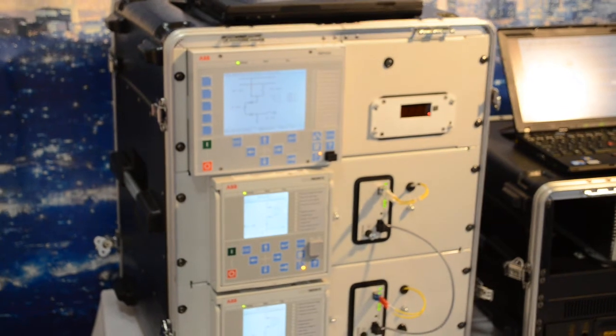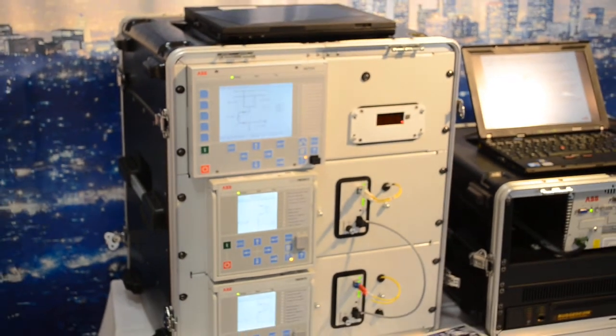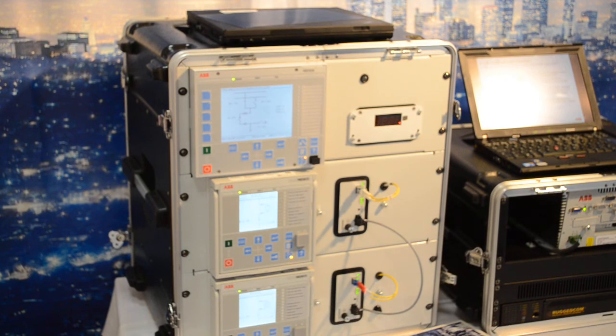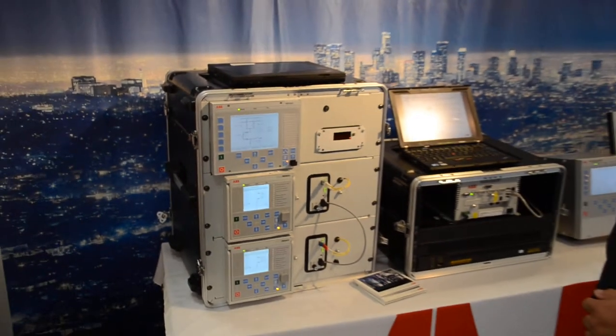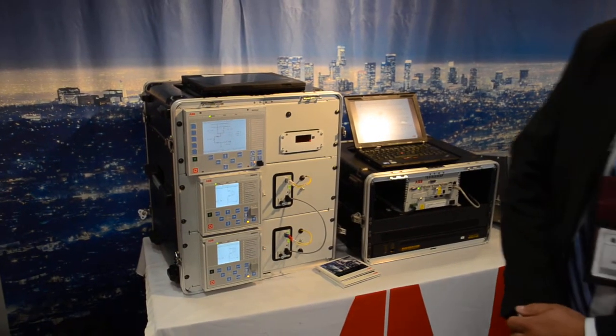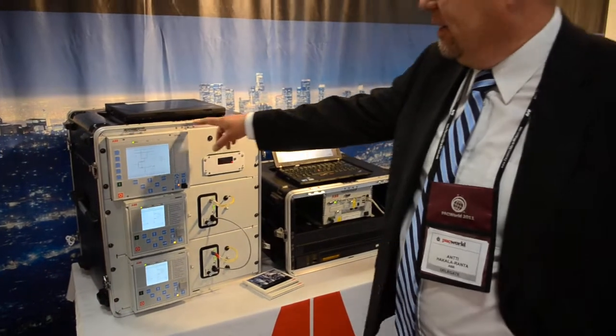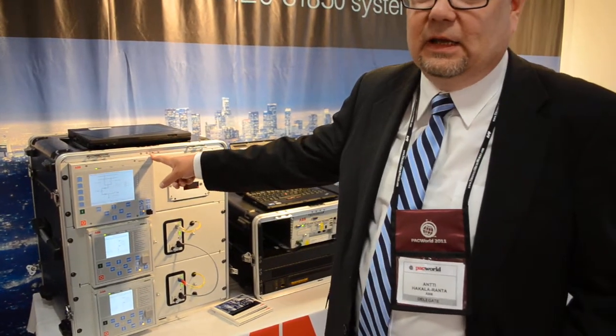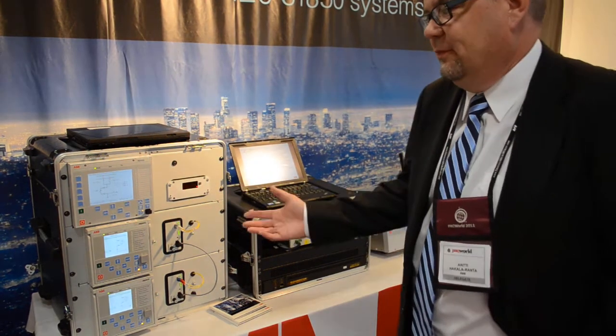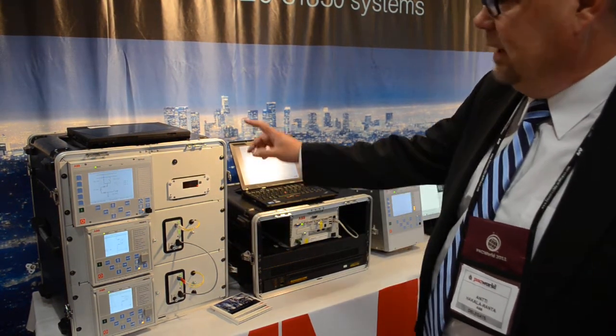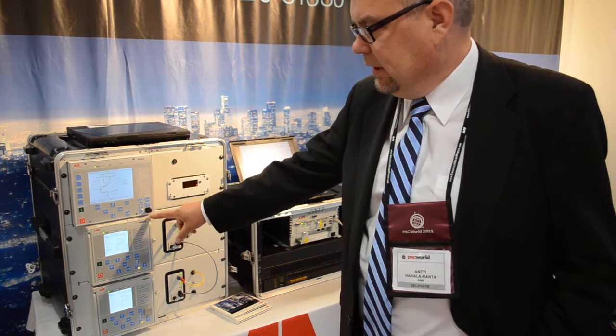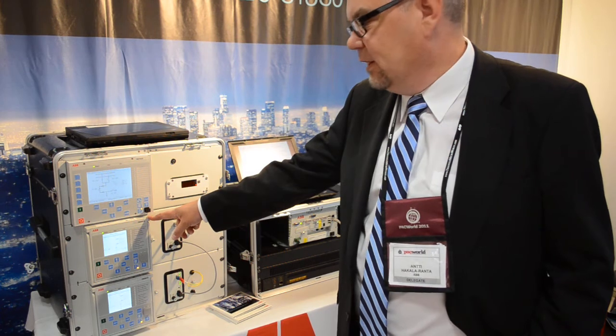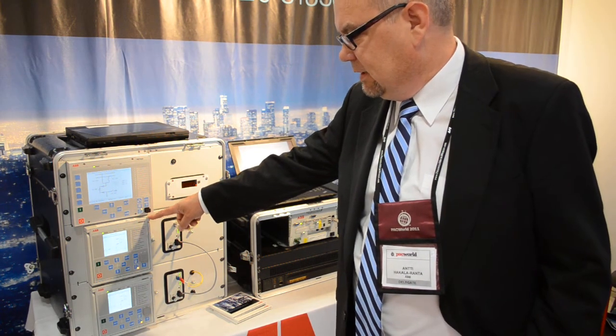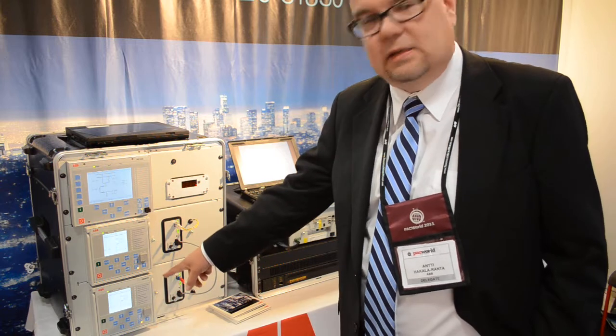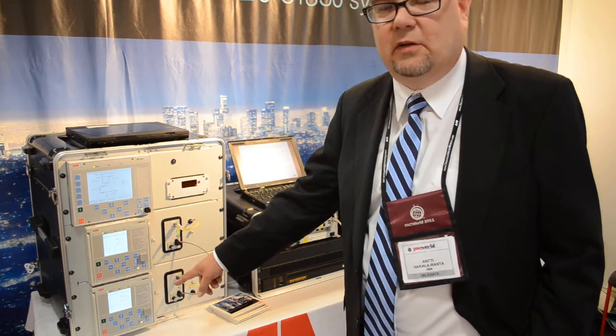What we are demonstrating here is how quickly the new communication system can be used to trip the outpost generator in case the main grid is lost. So, in practice, in communication terms, it works like this. The REF630 on the incoming feeder detects that the grid is gone or does the trip for some reason. Now, it will signal using GOOSE to the relay on the feeder, and that will send the signal over the line differential communication to this other relay, which will then trip the breaker on the generator end.